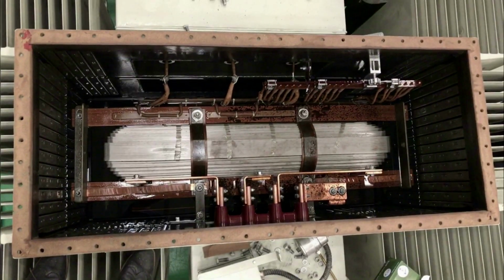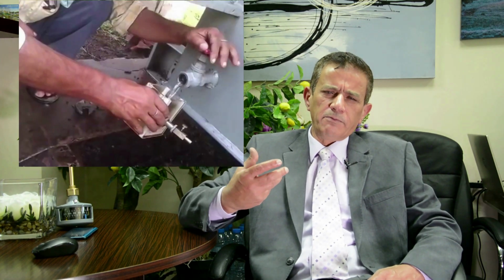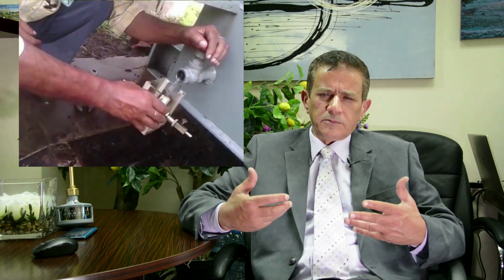Bismillah ar-Rahman ar-Rahim. The oil inside the tank of oil filled distribution transformer can be considered as a mirror which reflects the condition and the status of the transformer. We saw before, by taking sample from this oil, we can see if there are some foreign materials, some water content, some gases, some small particles from the insulation materials, from the paper and wood, resulting from corona or partial discharge from the winding. With time, sampling is important for inspecting the status of the oil filled distribution transformer.